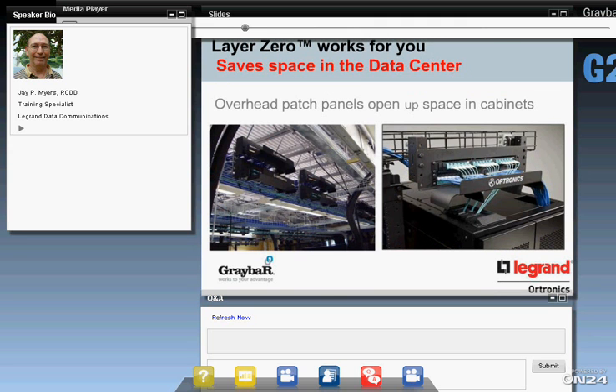So how can we save space? This is an overhead patch panel that bolts to the side of the cable pathway up above the cabinets. We built these for one customer as a custom item. As soon as other people saw the photos, they wanted them, so they're all now in our catalogs. They estimate that they could save 12 to 15% of the vertical space in their cabinets. So what that means is, by the time you put in 7 cabinets, you get the 8th cabinet free, and it doesn't take up any floor space. So these have become very popular.